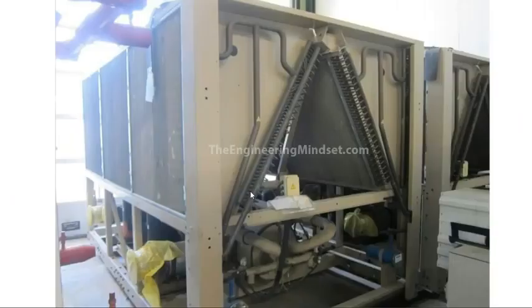Now I'll just give you a real world example here of some of the headers. So these are the distribution headers here, pushing that through. This one has got the flow and return, so it goes there and comes back. You can see it then runs into the filter dryer there. But anyway, we'll have a look at that in just a second. So it's coming from the compressor and making its way through these distribution channels, and you can see it teeing off there and going through the coils within this condenser to dissipate its heat.